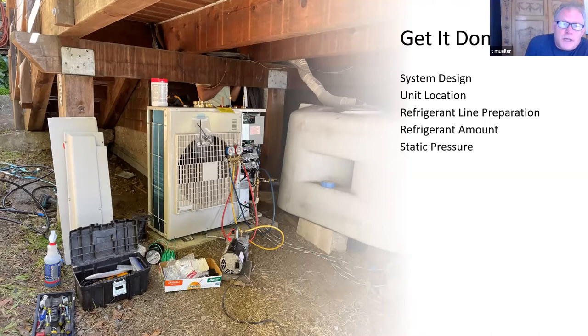Let's jump to unit location, which is a condenser location issue. Besides setback issues and stuff like that, there's performance issues on the condenser. You try to optimize performance by locating it in places that are as well ventilated as possible, ideally somewhat protected if possible. If it's a heating-only system, putting it out in full sun is not an issue, but sometimes it's unavoidable—it has to go in the sun—so there are just things to consider in that regard. It's not as critical as some of the other components, but certainly not to be neglected.